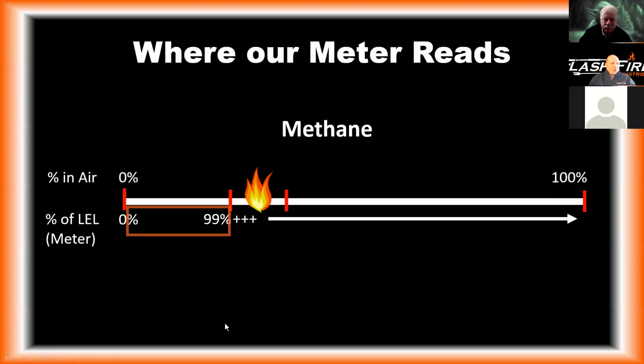Now, where is our meter actually reading? So the orange box is where that LEL sensor is actually reading. Okay. So it's not reading inside the flammable range, and it's not reading above the flammable range. Our LEL sensor for methane is only reading in the 0 to 100, I call it 99%, range. Our meter does not read in this area above here. We only read in the LEL range. So if we go above 100%, I have no idea if I'm in this LEL range, if I'm actually in the explosive range, or if I'm above the explosive range. Our meter does not tell us that. That's important to remember.